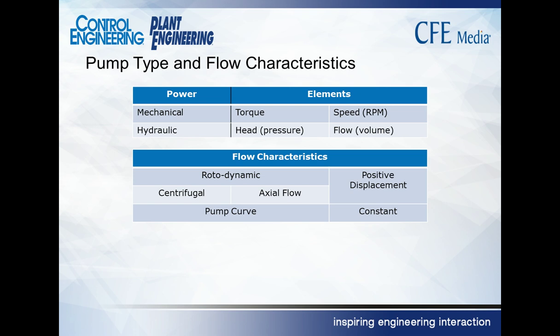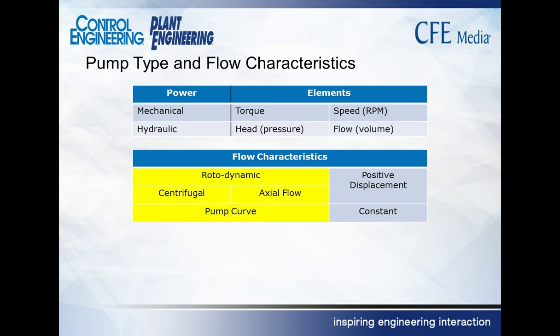There are a lot of different types of pumps out there. The two general categories are positive displacement and rotodynamic. Positive displacement pumps do not have pump curves. They have a constant relationship between pump speed and volume. But the rotodynamic pumps, both centrifugal and axial flow, do have pump curves. It's these rotodynamic pumps that have pump curves that we're going to focus on today.